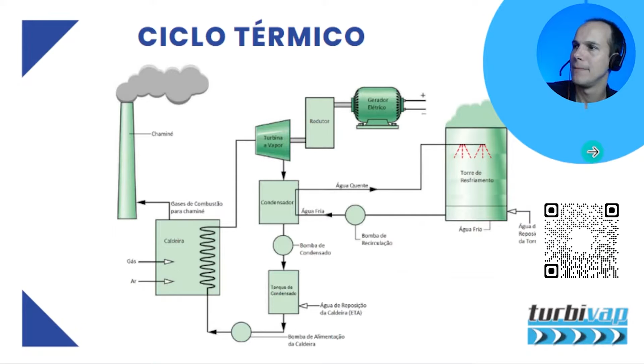The expansion of steam in the expander causes high speed, producing force on the blades mounted on the periphery of the wheel. So basically the steam is directed against the aerodynamic profile of a blade, and this blade receives the steam pressure, transmitting rotational movement to the shaft. If you look at the graph here, in this concept of design, the steam velocity decreases when passing through the blades of the moving wheel, however the pressure remains stable. A pressure drop still occurs, but it is very marginal, even negligible, disregarded for study purposes.